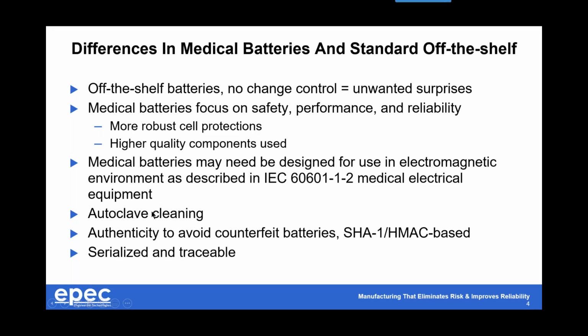Autoclaving, very high temperature cleaning, we see once in a while. Most off-the-shelf batteries would fail miserably under that environment, and even a lot of medical batteries struggle quite often. We avoid it if possible, trying to remove the battery from the product if at all means necessary.